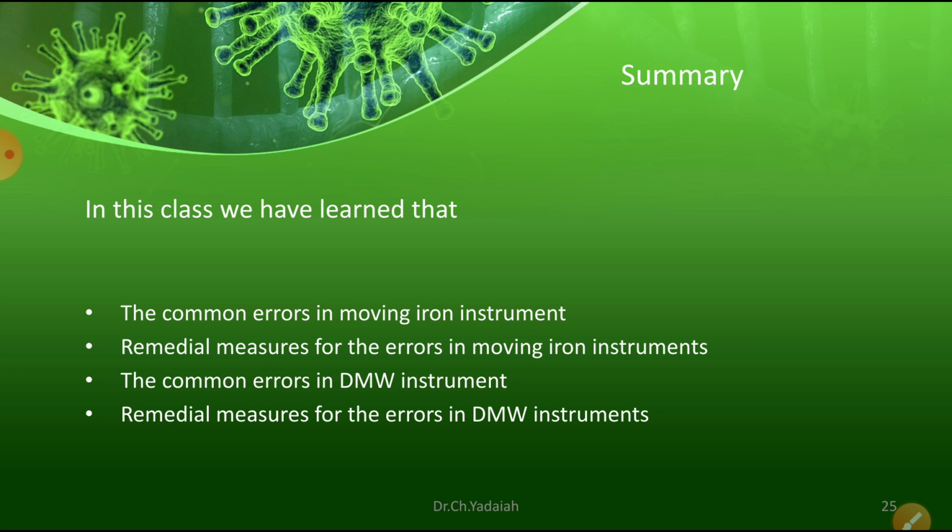The errors in moving coil instruments are mainly the temperature error. Change in temperature is directly proportional to the change in the coil and spring temperatures, thereby the deflecting torque and controlling torque change. That can be avoided by connecting a manganin resistor in series with the voltmeter, whereas a shunt is used across ammeters.